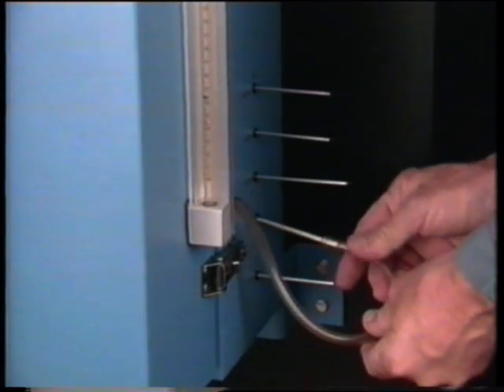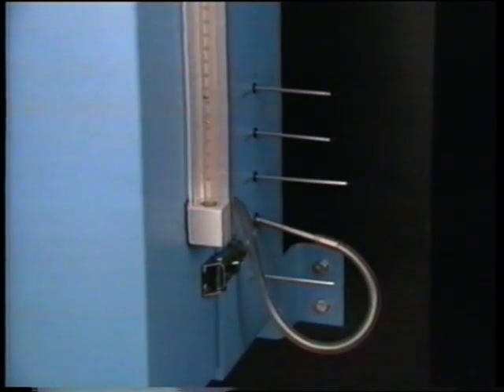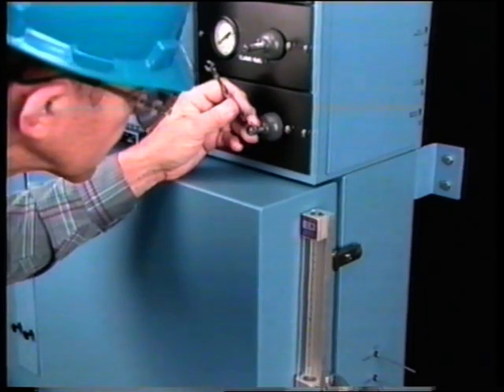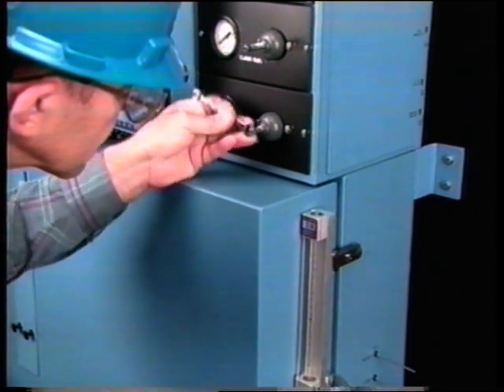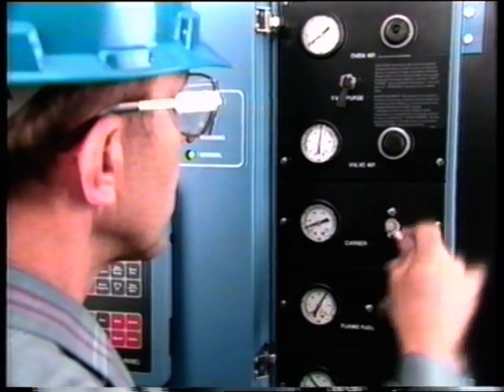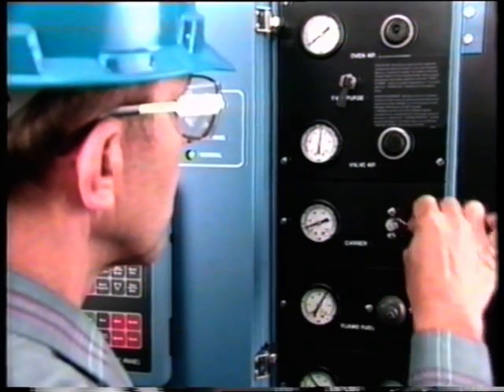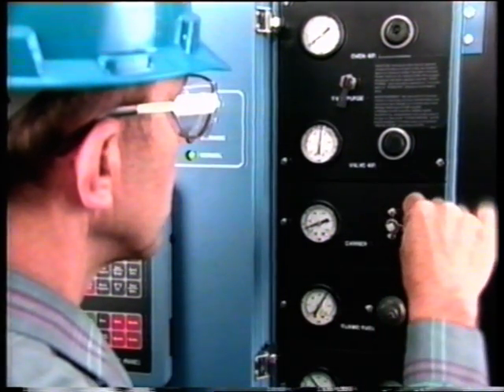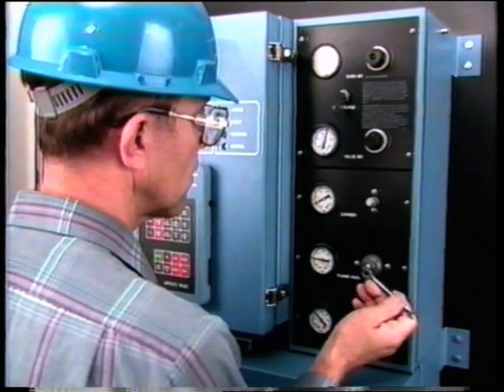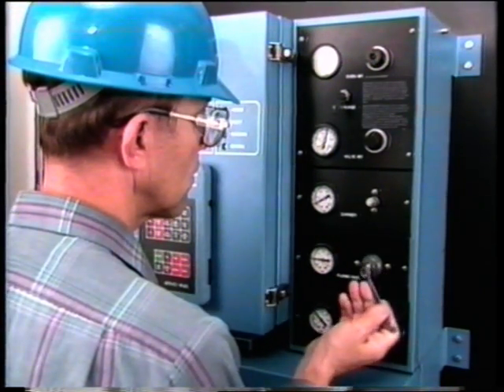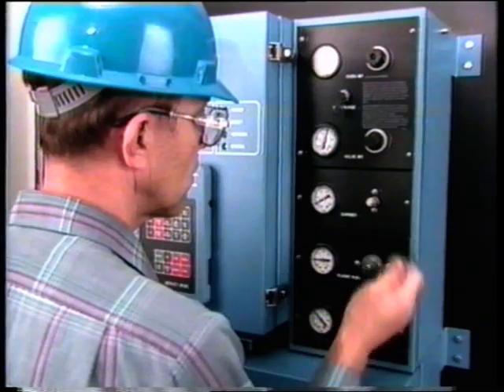Connect the 800 cc rotometer to the detector vent and adjust the flame air regulator to 500 cc's per minute. Remove the rotometer and adjust the carrier regulator to the proper pressure. When maintaining the detector, the flame must be out and the analyzer power turned off.